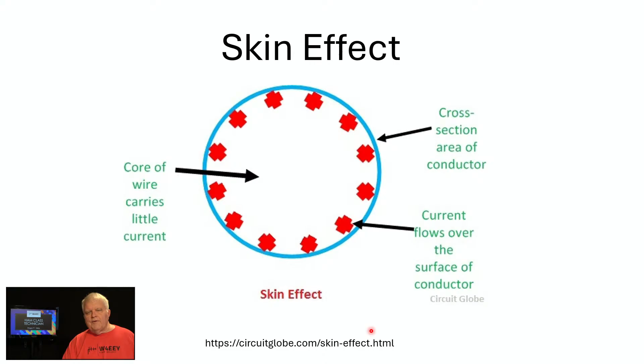So on skin effect, here we're looking at a cross section of the wire. RF current flows on the outside of the wire, just on the surface of the wire. On the inner part, there's very little current, and it varies with frequency, but the higher in frequency you go, the more the skin effect takes place. At microwave, for example, there's nothing there in the middle, which is one reason why, for grounding and bonding, flat copper strap is preferred, because there's very little inside and there's a lot of surface area for RF current to conduct through. There's also very little inductive reactance with flat copper strap. So flat copper strap is the best conductor for radio frequency grounding because of the surface area.